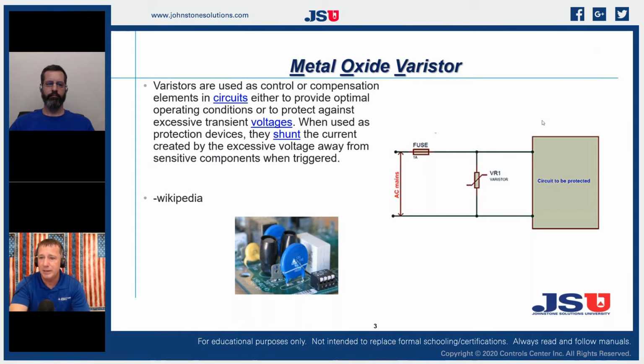So in the circuit, when we look at how it is installed into the electrical circuit, let me grab my Sharpie here. You'll see that we typically have some type of a fuse or a breaker in our system. So we have our main power coming in, and then we have our components. Let's just say this was an outdoor unit, a condensing unit, but it's an inverter outdoor unit, so it's got circuit boards on it. Typically we're going to have a fuse or a breaker in our line, and what we do with the varistor is that we bring it between our lines, and then we direct current away from that actual appliance. So it's in the circuit, typically as a parallel component.